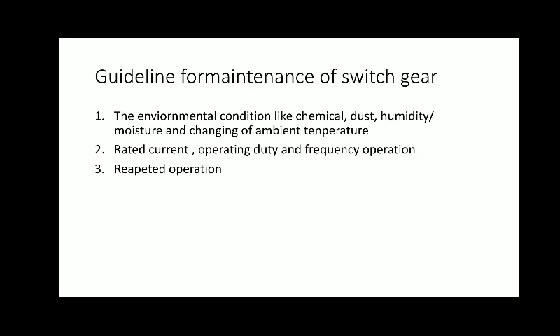Next one, repeated operation. If there is a repeated operation, that is switching, that is an operating duty or switching duty. Then guidelines are obtained from the manufacturer. It is difficult to get the exact manufacturer schedule meeting local requirement of each site. So the maintenance schedule is framed after initial periodic inspection at the site.